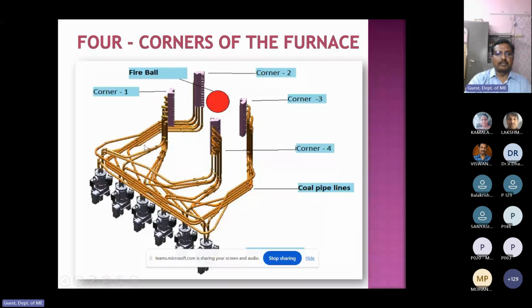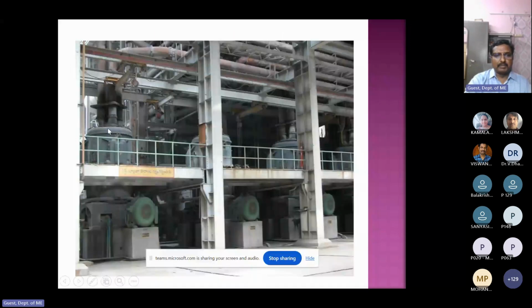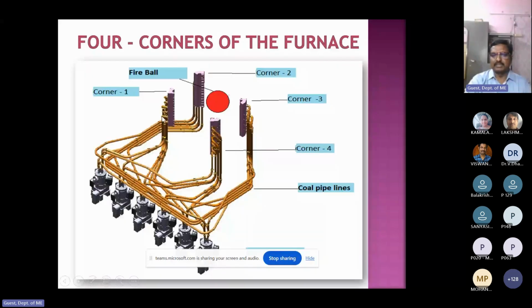From the top of the bowl mill, there are four lines. There are four lines from each mill. Each line goes to each corner of the furnace. This is the furnace of the boiler. So these are all bowl mills. From each mill, there is one line. It goes to each corner. So each mill supplies one elevation. One elevation, one by one, there are 6 elevations.